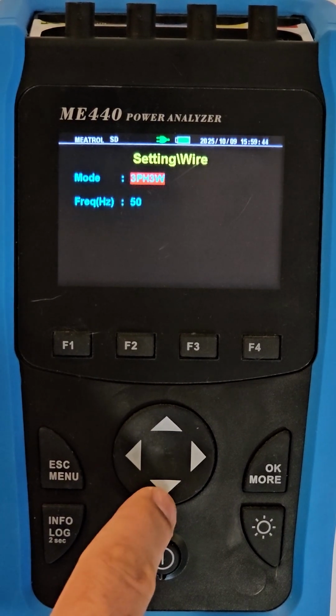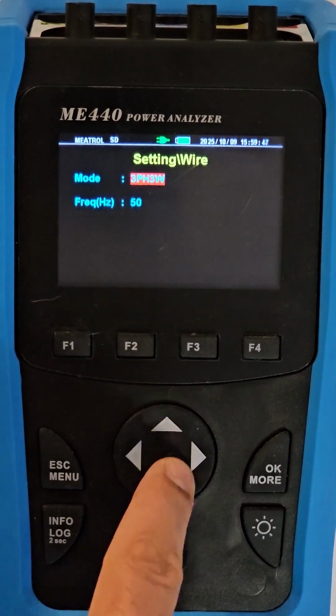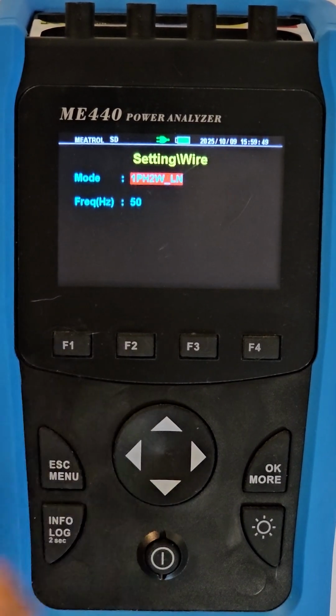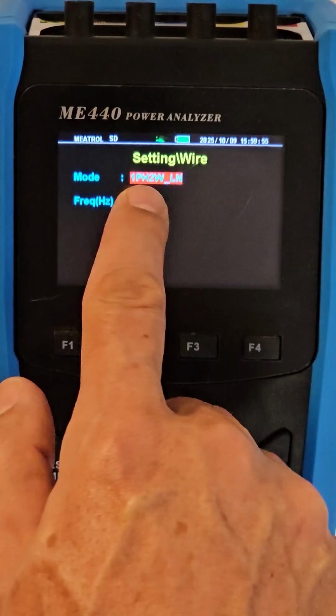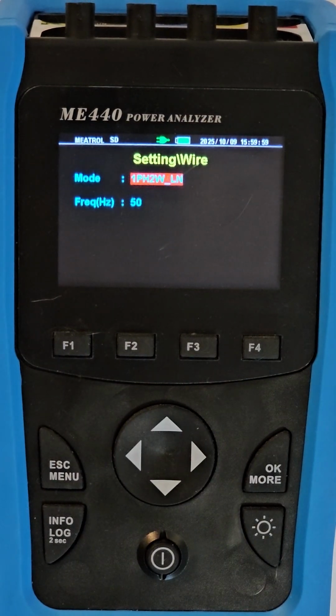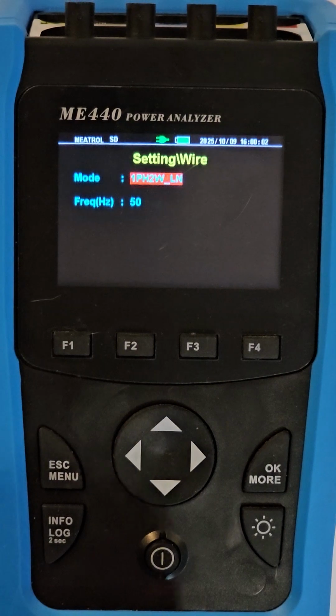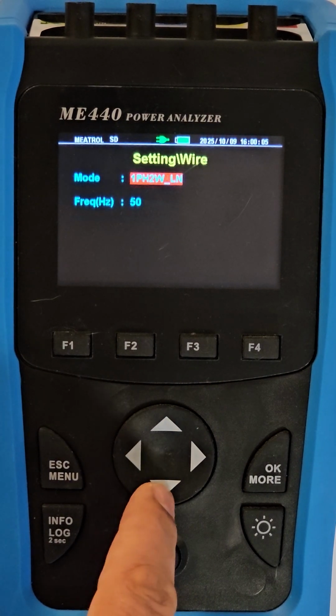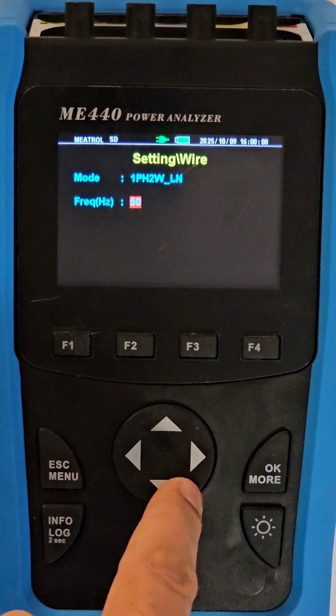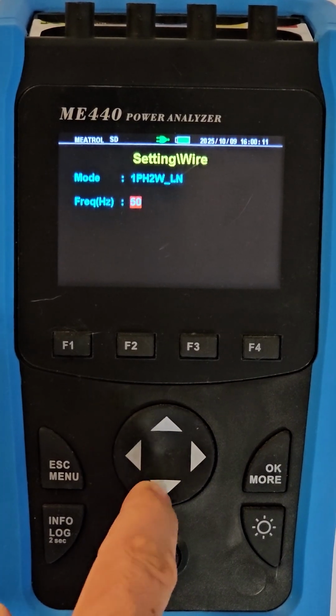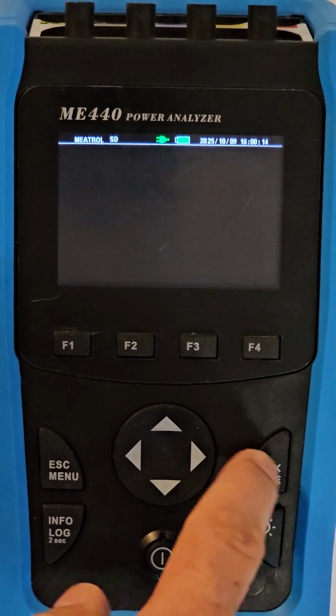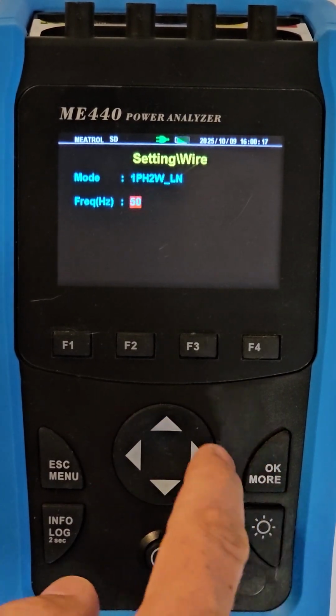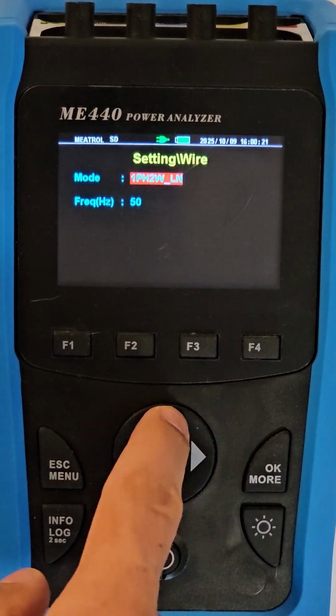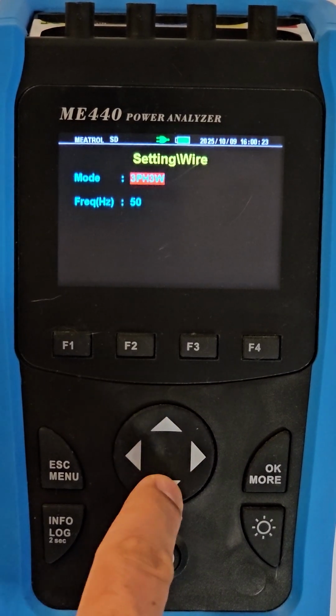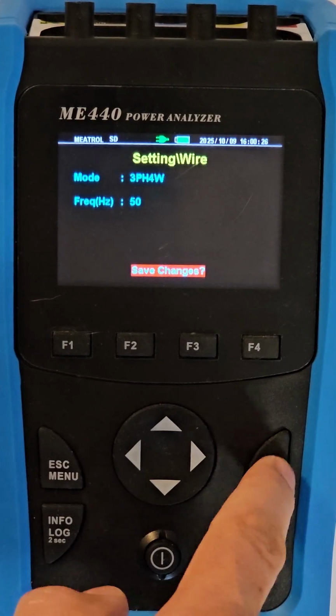Okay, and then, yeah, to measure normal single phase you use 1-phase 2-wire, live neutral. That's the setting that most other countries use for single phase. Good. Okay, and then you can also change the frequency either from 60 Hz or 50 Hz, also normally 50 Hz. Let's just change back to 3-phase 4-wire. Okay, good, and save your changes.